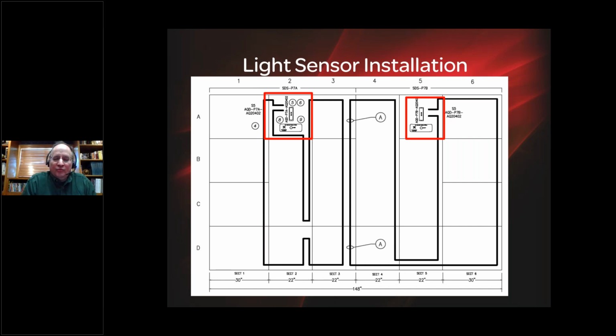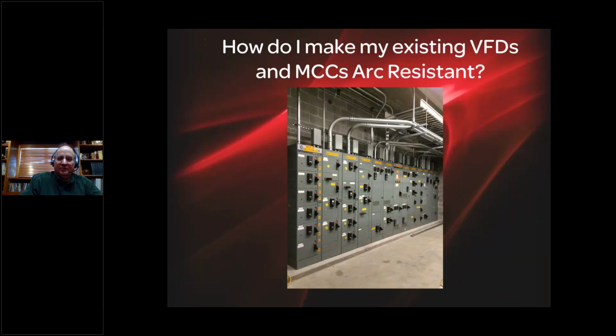Now, remember that the arc quencher must have a device on the line side above it which is trippable. But provided that the switchboard is as I showed in the earlier picture here, hold on a second, let me get to it.